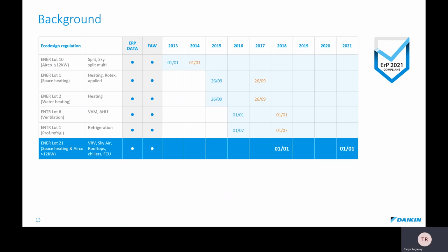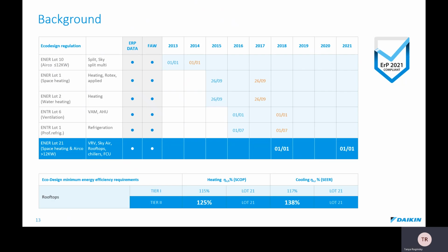Daikin is following the eco-design regulation for different HVAC products. Rooftops fall within the Lot 21 framework, together with the largest SKY systems, VRVs, and chillers. Since 2018, when it first came into place, Daikin had to meet specific energy efficiency requirements. From the 1st of January this year, we have moved into the Tier 2 framework for Lot 21, increasing these minimum primary efficiency requirements. This resulted in a massive change in the requirements for rooftop products, so we had to redesign and bring forward the new range.